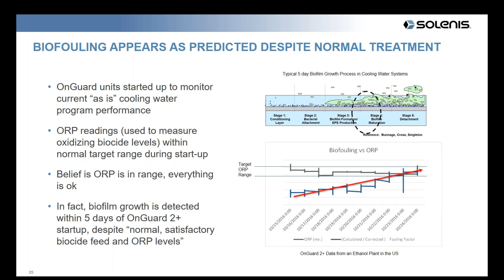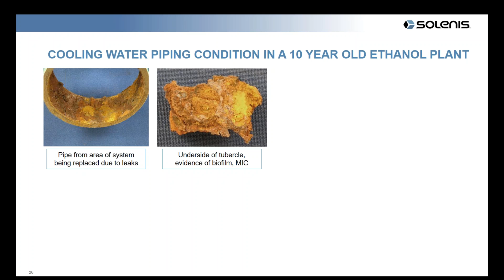The other thing we're seeing, which is very interesting, is a specific example from a 10-year-old ethanol plant in North America. These are sections of cooling tower piping system, mild steel piping being replaced because of leaks. We have a metallurgical lab in Wilmington that kindly shared metallurgical samples with us, and when we put them under the microscope and take off some of those corrosion sites, you can see very clear evidence of what Tim calls MIC, microbiologically induced corrosion, occurring on the pipe.